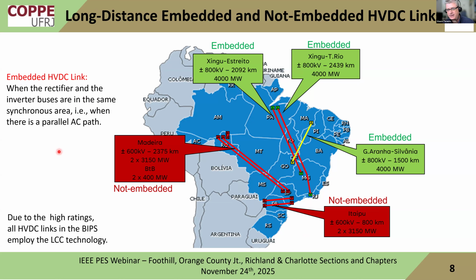That's just when there is a parallel AC path. In these two cases, Madeira and Itaipu, there is no AC in parallel, because they connect radially very large hydropower plants into the system. So you can consider those HVDC links part of the generation. Due to the high ratings, we're talking about 4 gigawatts in this bipole, another 4 here, and 4 here - actually this one is 5, it's wrong here.